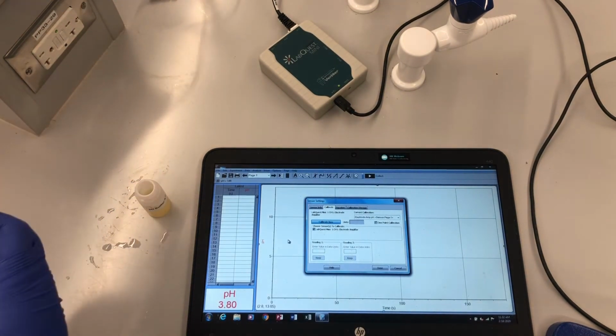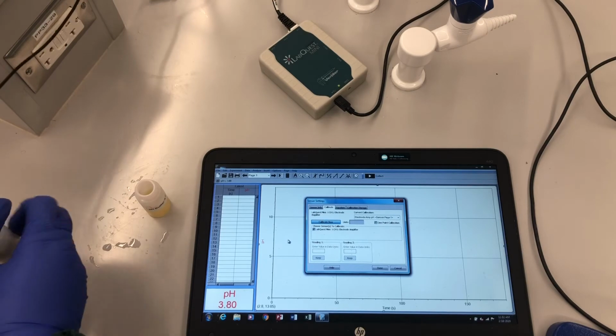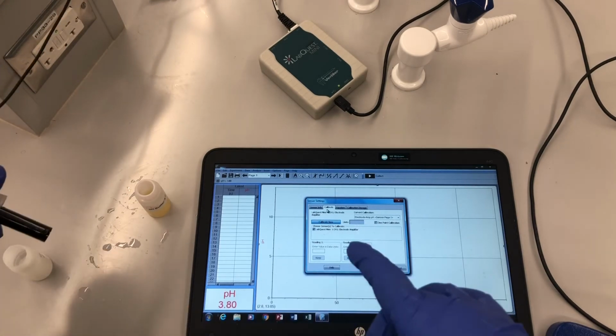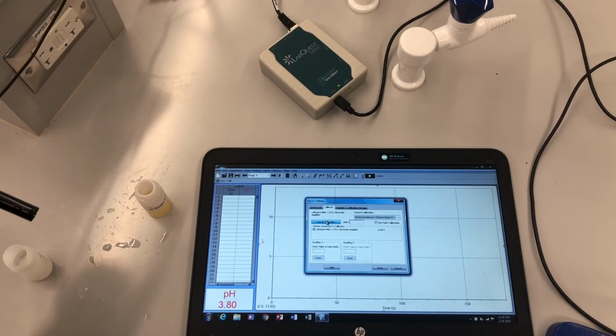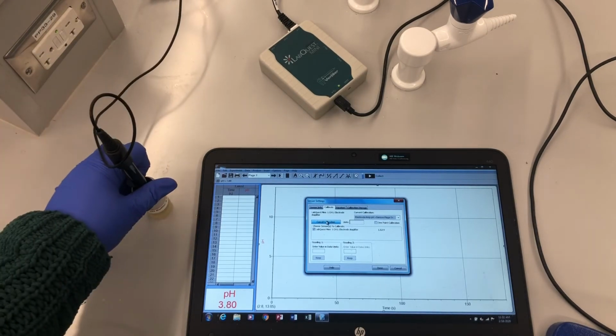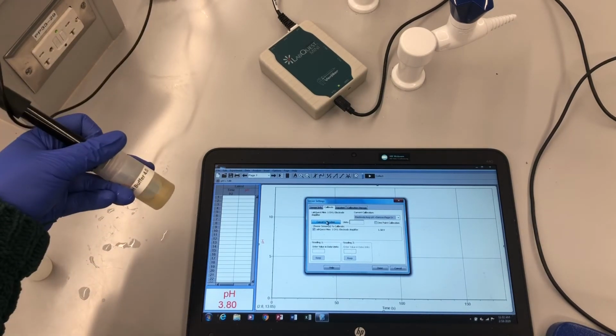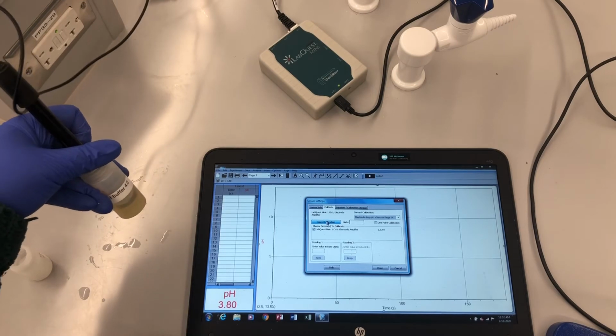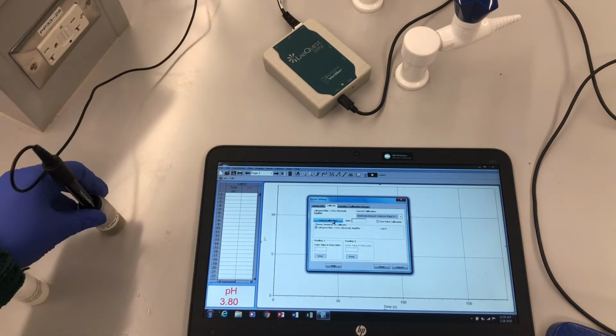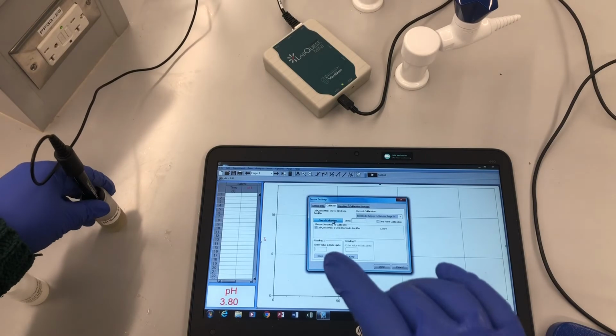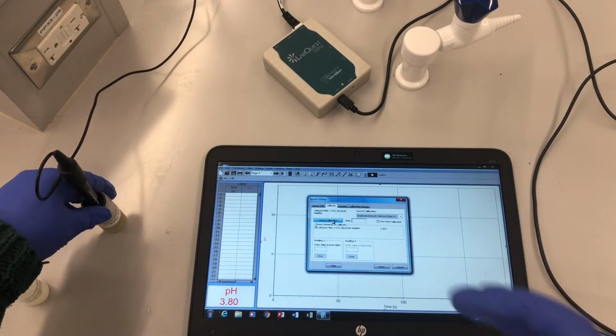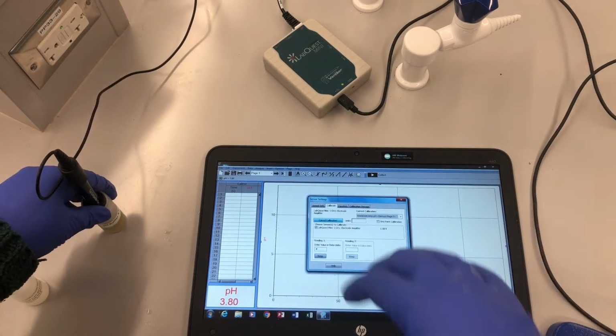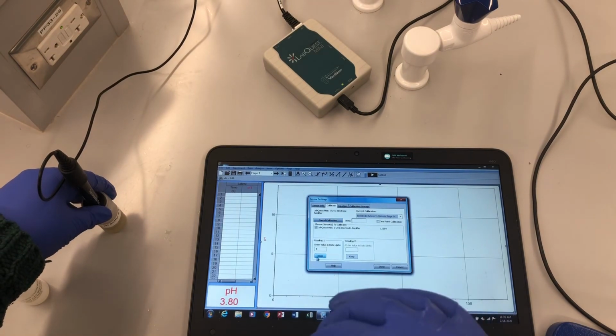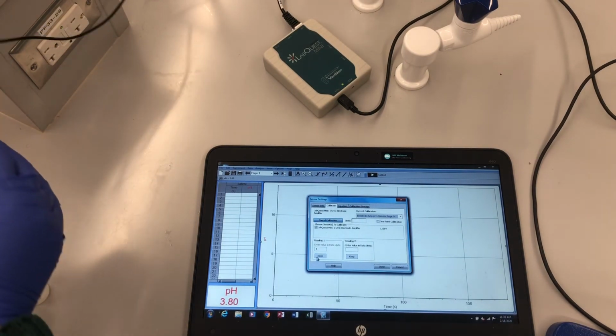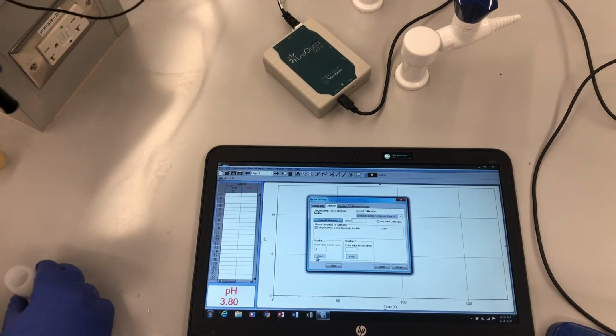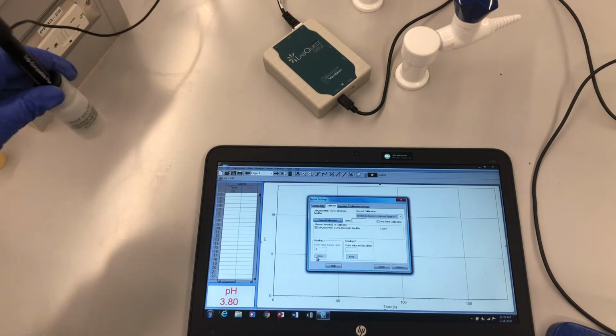Just go in here, take our probe out. I'm going to hit Calibrate now. Stick my probe in. And you need to let the probe sit in the sample for a little while. And this is true whether you're calibrating or taking measurements of your water sample. And I'm going to have to let it stabilize for about 10 seconds. So once you give the allotted time, go to 4 and hit keep. I'm going to take it right out, stick it right back in the storage solution.